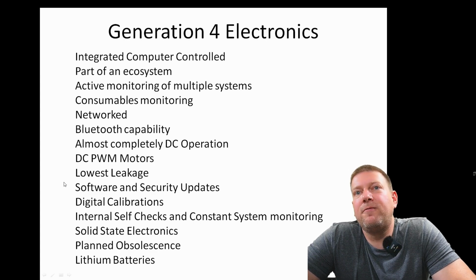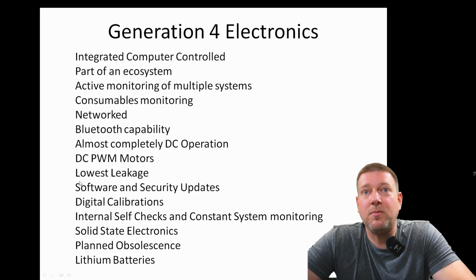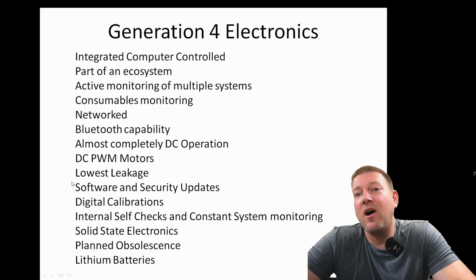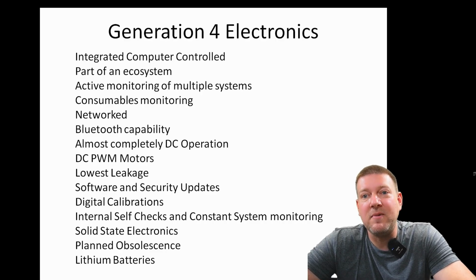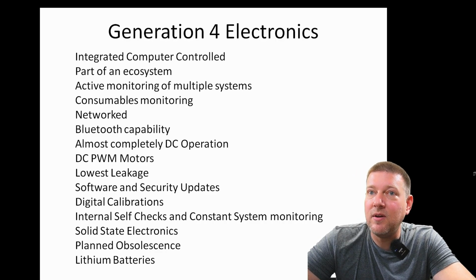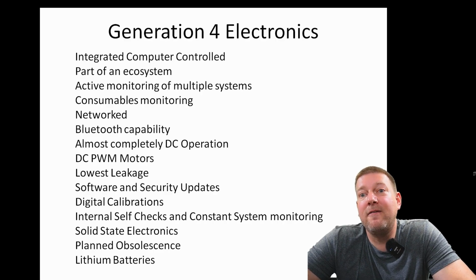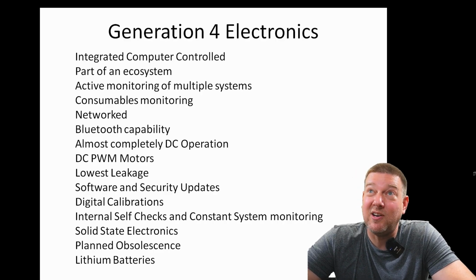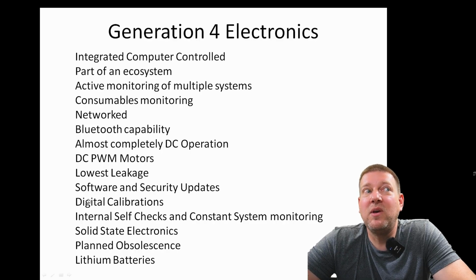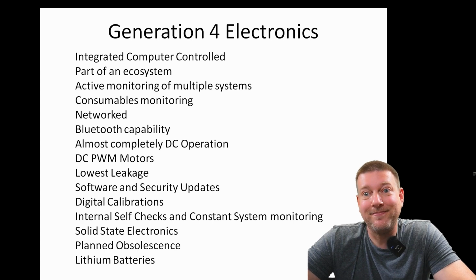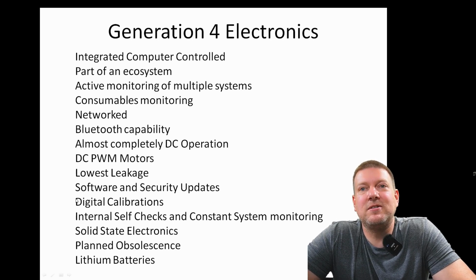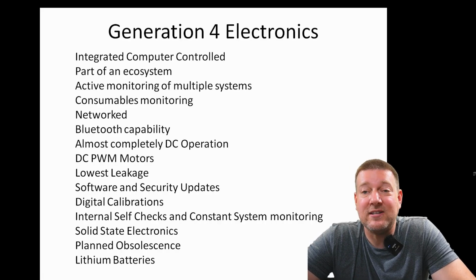A big indicator of Gen 4 electronics is there are software and security updates. Yes, there's software licensing options, but now you have to regularly upload software to keep your device current. This is a big one for Gen 4. That means usually you have to have some sort of subscription, and you have to have the OEM touching your device, usually. So Gen 4 is also when we get into flat rate repairs and stuff, because only the OEM can touch the device. There's also digital calibrations, and we usually do not have access to those digital calibration screens.